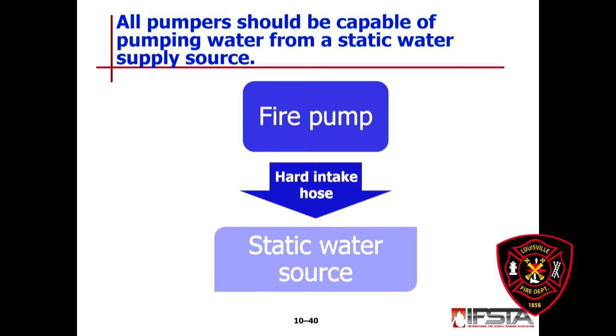Every fire pump should have the capability of doing this, and this is how we test our pumps when we draft. And again, as I said earlier, that plate on the side, when we say that our pumps are rated to pump 1500 GPM, that's at a draft. So things we need, obviously the fire pump, a hard intake hose, a hard suction is what we call it, and then obviously the static water source.